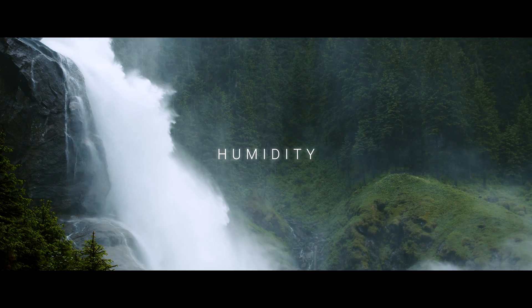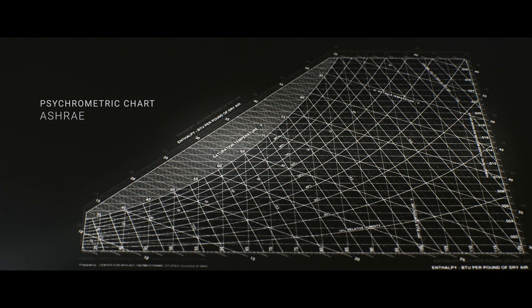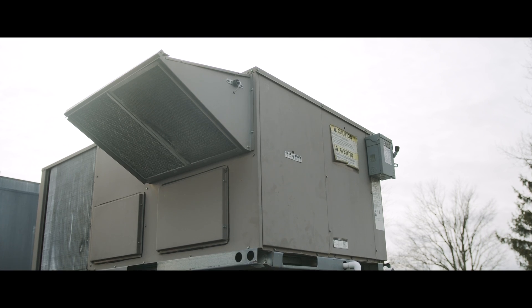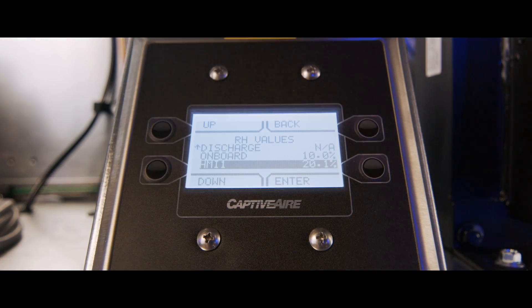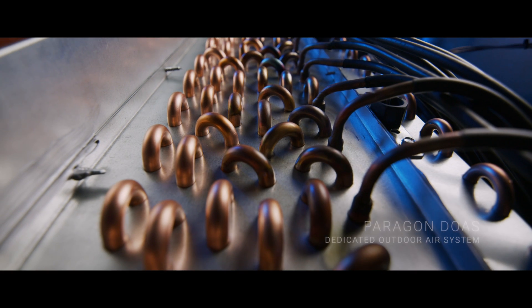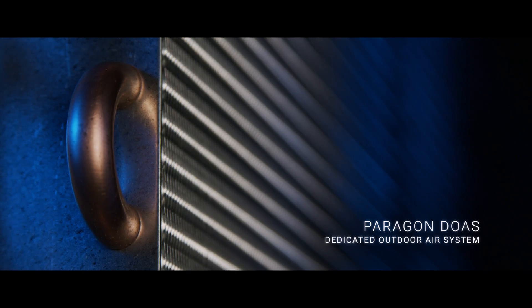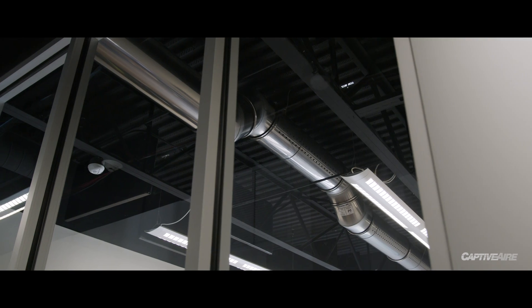When you look at building comfort, you have to look at both temperature and humidity. Different humidity levels can make the same temperature feel much different. Traditional RTUs do not control humidity levels in the space — they try to by running the cooling a little longer, but we know that's not a good solution. The way DOAS can control humidity in the space is by using a very thick coil, forcing the air to interact with that coil more efficiently and for a longer period of time. It cools the air molecules down below its dew point and drops moisture out of the air, then warms the air back up to deliver it to the space in a comfortable range.